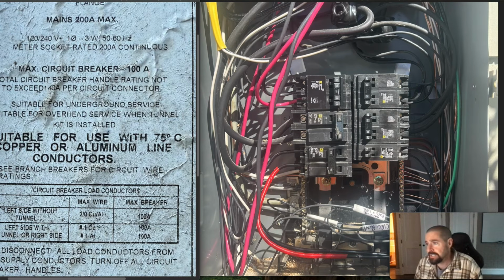You'll oftentimes see 125 amps, things of that nature. So in this case, there's just no larger breaker than 100 amps that you can connect to this panel. So you're just limited by the equipment up to 100 amps of backfeed. Now, when it comes to solar and storage, if you're backing up home loads downstream of the equipment, that also kind of runs you into this issue of, well, you only can connect a 100 amp breaker to feed your microgrid interconnect device or your transfer switch.